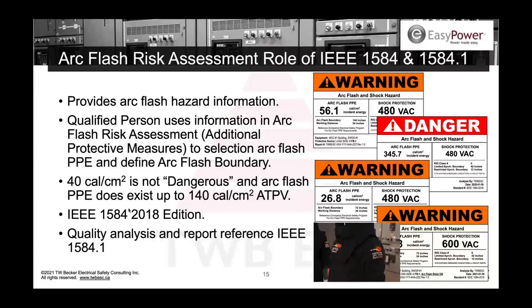All right. So again, bridging this to the calculations, ultimately that's what you're delivering. So 1584 says calculate the incident energy at a working distance and the arc flash boundary. And then you provide example arc flash and shock labels in your report. These are compliant labels. So I continue to try to influence the implementation or the recommendation of compliant labels to ANSI Z535. And again, so that the worker can get the information they need. They understand where the incident energy is on the electrical equipment. It's quite clear to them. There's a lot of arc flash labels that have been provided over the last 10 years that are not compliant. So we need to continue to influence what this compliant arc flash and shock label is.